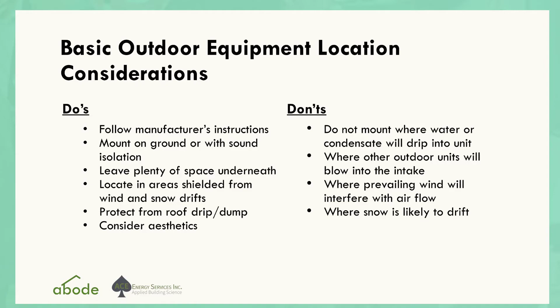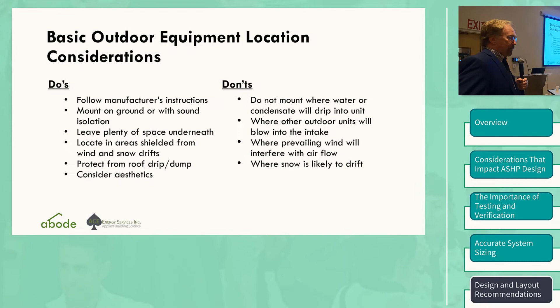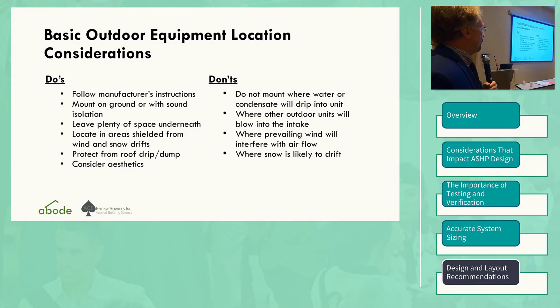Do's and don'ts for outdoor equipment location: absolutely the most important thing is to follow the manufacturer's instructions, really don't veer from that. Mount on the ground or with sound isolation - we put them all on the ground because they vibrate the house, unless it's a room way out of the way, but especially with an older 2x4 home they can really transmit vibration. Leave plenty of space underneath, shield it from snow drifts, protect from roof drip, and consider the aesthetics. Don't mount where water condensate will drip, or where outdoor units blow into the intake. Prevailing wind will interfere with the airflow, and watch for where snow is likely to drift.